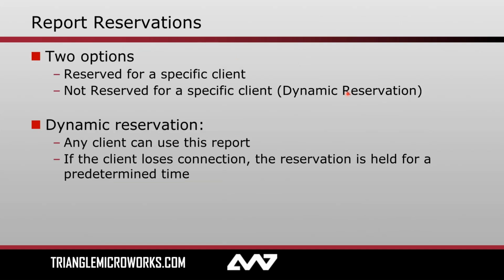So before I dive in deeper on buffered reports, just a quick word about reservations. Basically, when you're designing your system, let's say as a substation engineer, someone who's actually responsible for the configuration of the SCADA communications, you have two options when designing a report control block. Do I want to reserve this report for a specific client? For example, let's say I'm designing a report that I know I want to be passed to my SCADA system, and a second one that I know I want to be passed to my local HMI or historian. I have the opportunity during the design phase to define reservations so that a specific report can only be enabled by one specific client. The other option is not reserved.